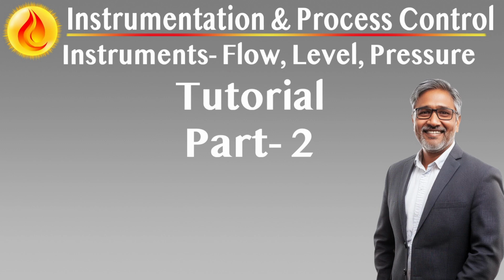Accessibility engineering to ensure maintainability, safety, and operational uptime. Instrument accessibility must be engineered with the same diligence as process design. It directly impacts field safety, maintenance effort, and instrument uptime. Accessibility is not just about physical reach. It defines whether routine calibration, inspection, and troubleshooting can be performed without scaffolding, crane intervention, or process shutdown. 4 standardized accessibility classifications must guide layout decisions.